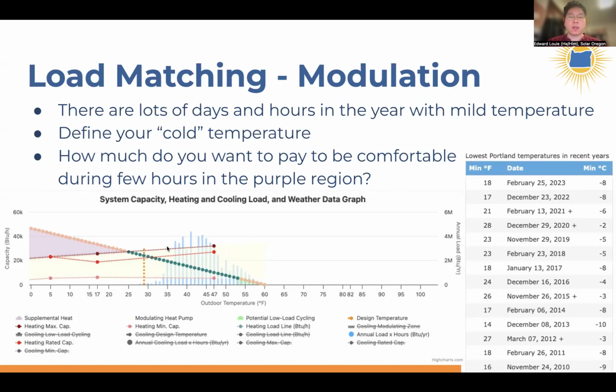And there's not going to be a heat pump that can generally do it perfectly. For example, in the previous slide, I mentioned that the example heat pump can modulate down as low as 9,000, maybe 10,000 BTUs. Well, if it's 55 or 58 degrees outside, the heat load of this example home is so low that it falls below the 9,000 BTUs. So even a modulating or inverter driven heat pump can't modulate low enough to match the load, and it will still turn on and off and cycle on the extremely mild days.